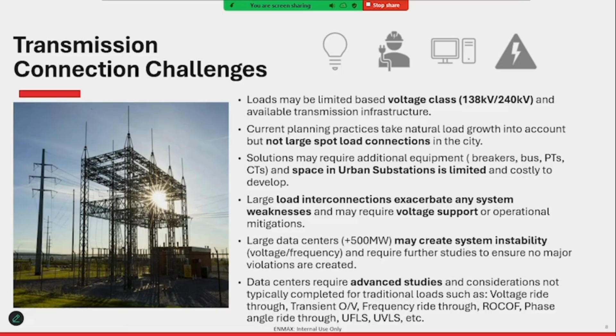On the last slide, some transmission interconnection options: existing site expansion, adding a transformer, or building dedicated transmission lines, but space is limited. There might not be room for a high voltage breaker or other auxiliary equipment like potential transformers, current transformers, or bus expansion.